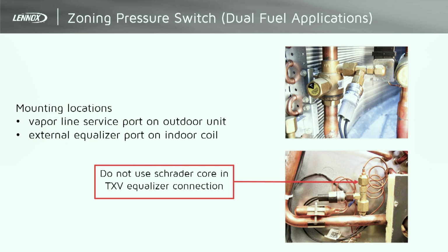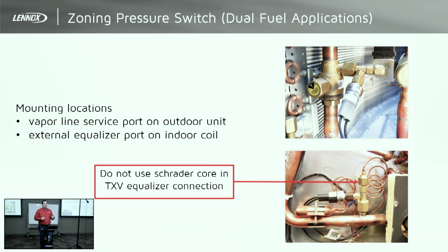So again, this is just one of those things that is an easy step, but in the heat of battle, when you've got 1,000 things to do, it's an easy little step to miss. So just make sure that if you do end up putting one of these in, the purpose of that port is to have a Schrader so that if you install it on the outside unit, you can still hook up a gauge set. But if it goes inside, you've got to make sure and take that Schrader valve out of there. Any questions about that?